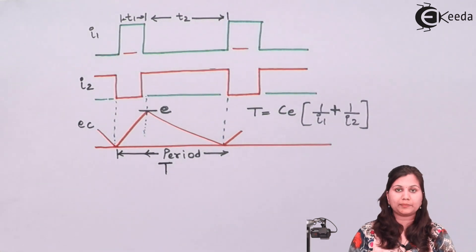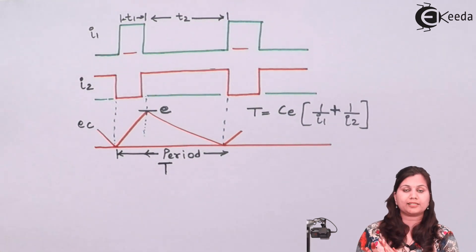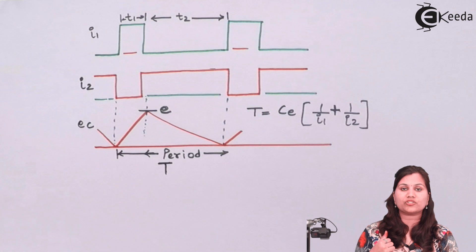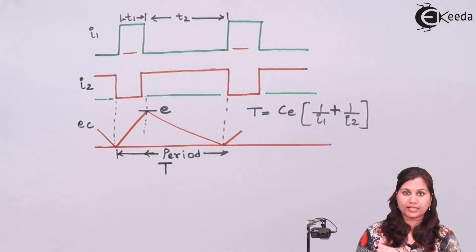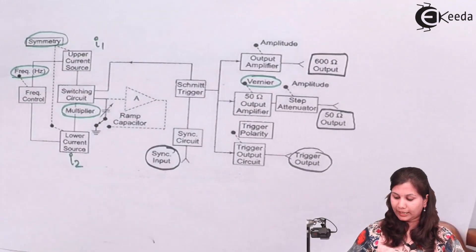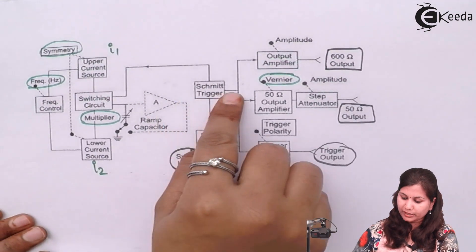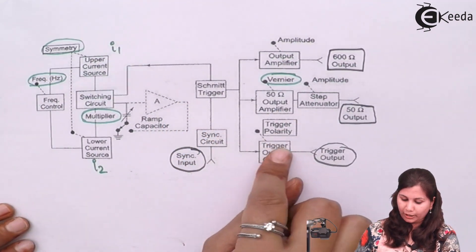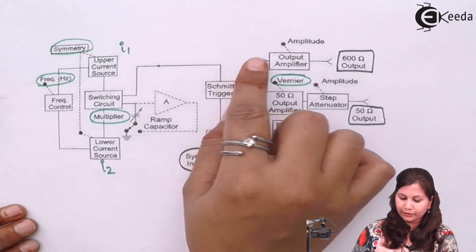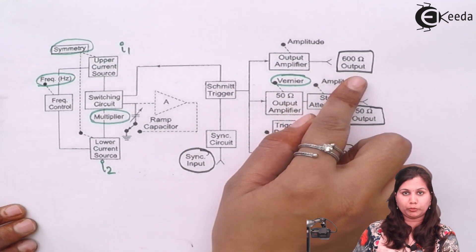The whole process repeats: the capacitor is charged, then discharged, and the Schmitt trigger changes its state at each stage. The output of the Schmitt trigger is passed to the trigger output circuit, to the 50 ohm output amplifier, and to the 600 ohm output amplifier. So this same output is given to three outputs.